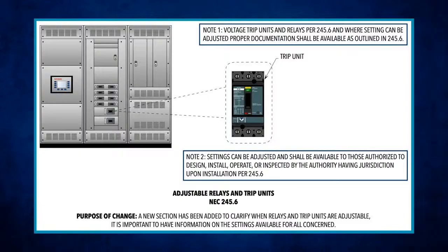245.6 is a new section dealing with adjustable relays and trip units. Basically, where you have settings on these relays or trip units that can be adjusted, documentation of those settings will be required to be available to anyone authorized to design, install, operate, or inspect the installation, and of course available upon request to the AHJ.